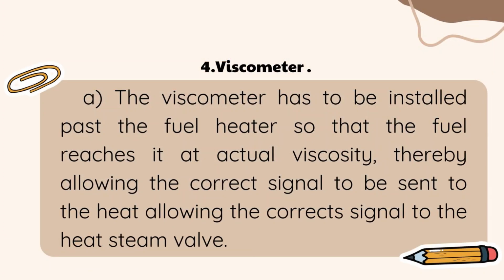4. Viscometer. A. The viscometer has to be installed past the fuel heater so that the fuel reaches it at actual viscosity, thereby allowing the correct signal to be sent to the heat steam valve.